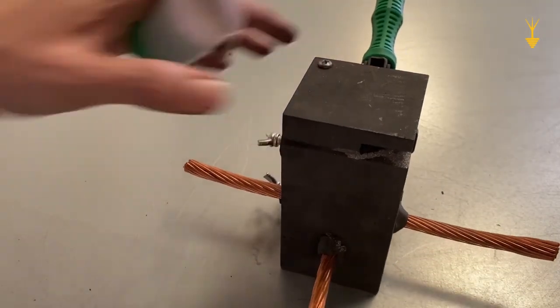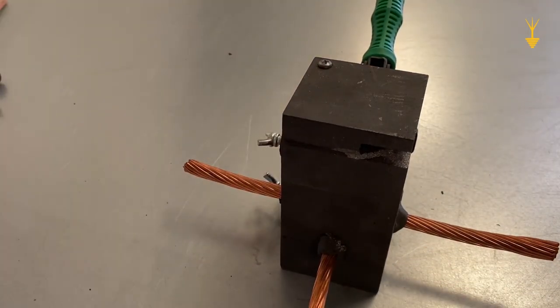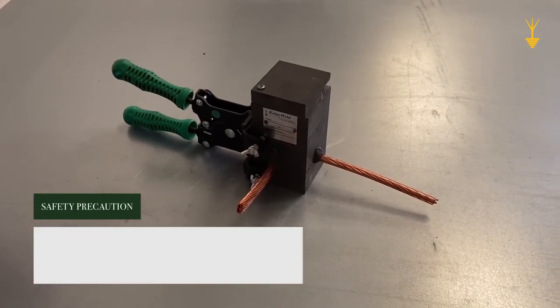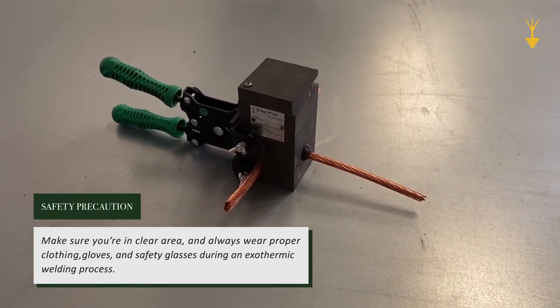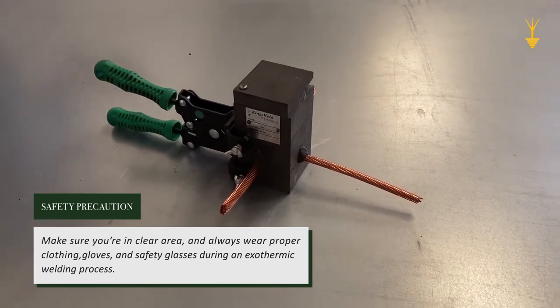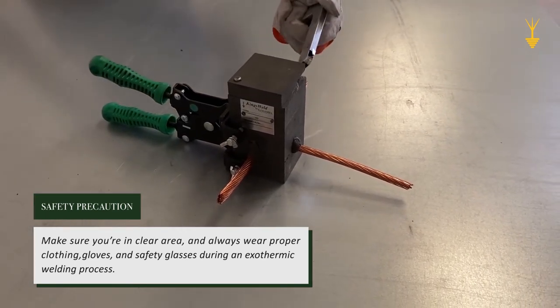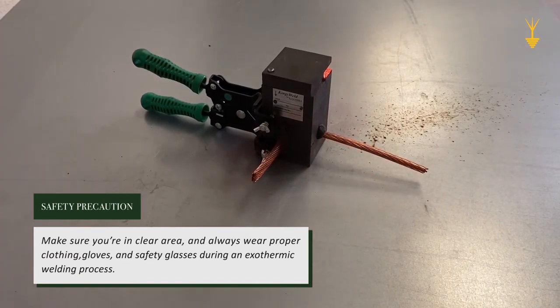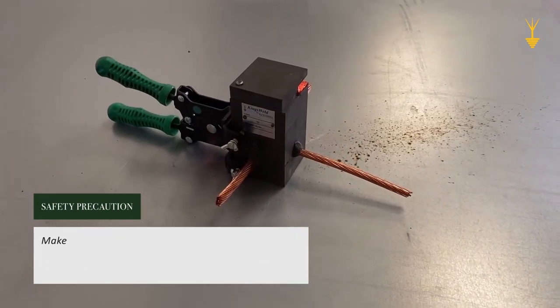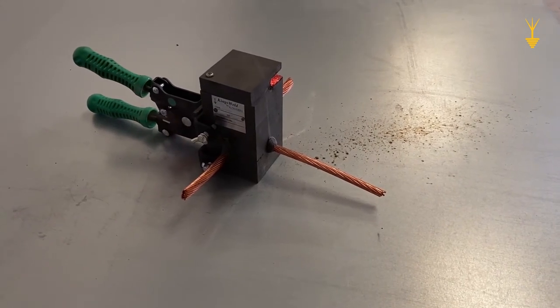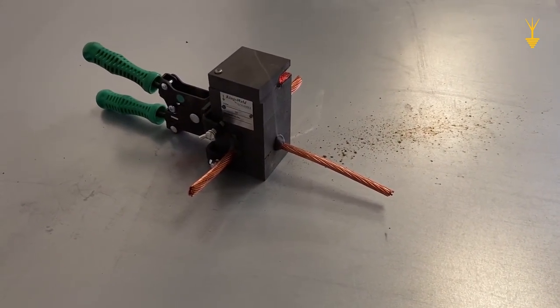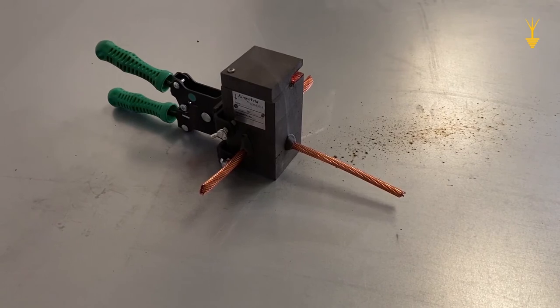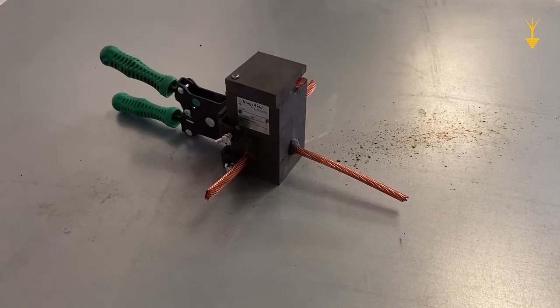So, now, we're ready to light the fuse. Now, make sure that your surrounding area is clear, and that you've got your safety gear on, and then go ahead and spark the ignition using a flint gun. Now, the reaction will go off. Let the mold sit for about 20 seconds, and then open the mold, and we'll go from there.